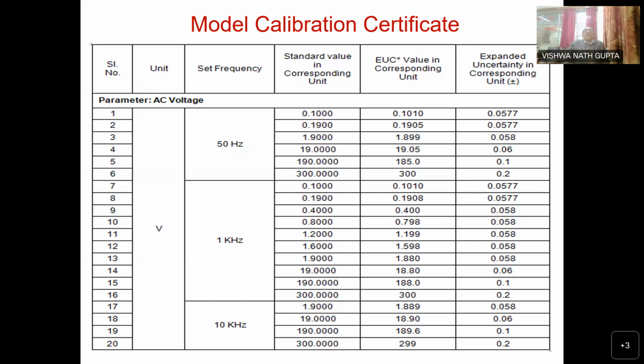So set frequency at 50 hertz means the standard value in the corresponding unit has been injected like this: 0.1 volt, then 0.19 volt, 1.9, 19, 190, 300. Then the same is repeated for 1 kilohertz and for 10 kilohertz, and in the next column the EUC value in the corresponding unit. This is for the example only, sir. Whatever result there is, we note it down and the calibration certificate is prepared on the basis of that. In the last column, the expanded uncertainty is given in the corresponding unit. Okay, sir.